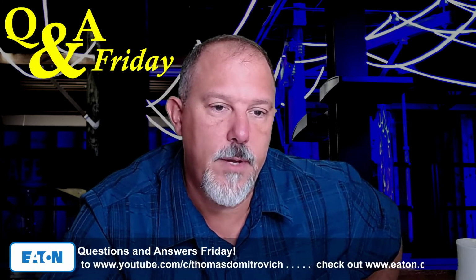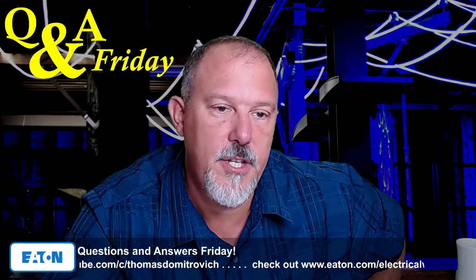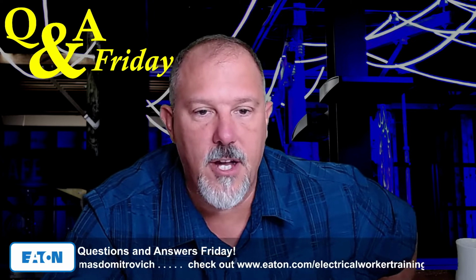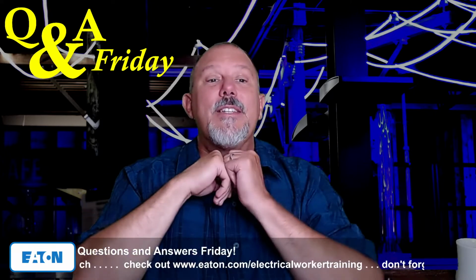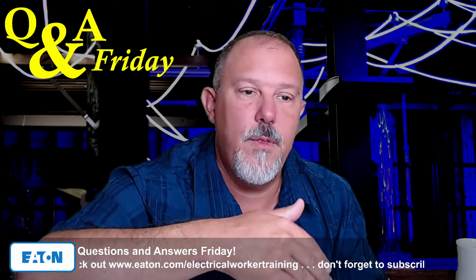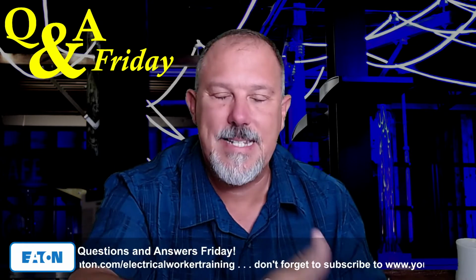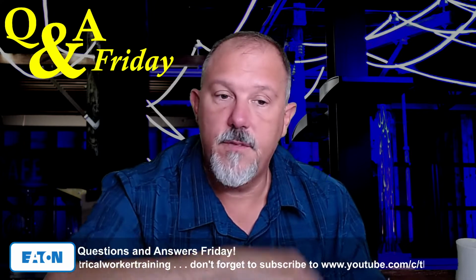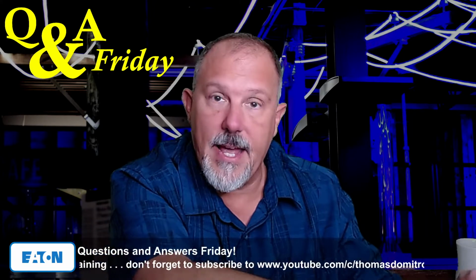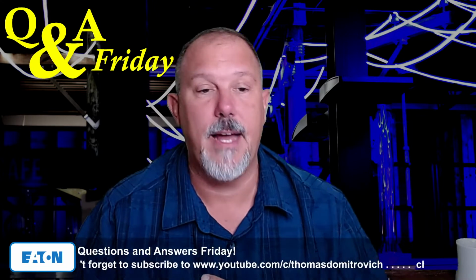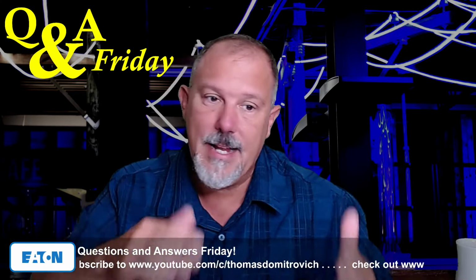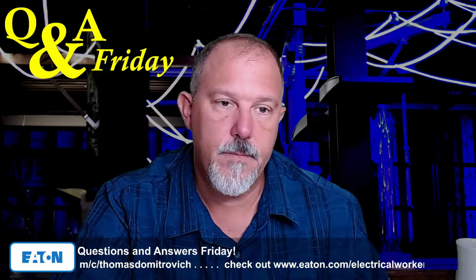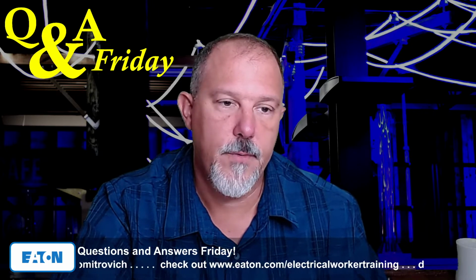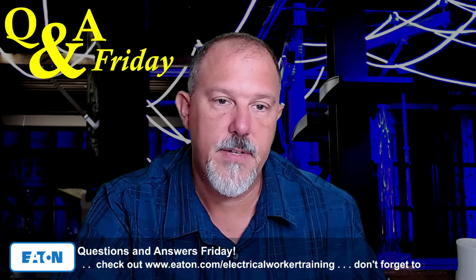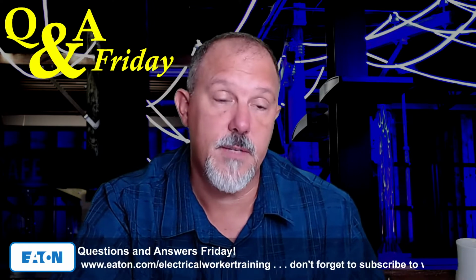As a result of 210, we now have people in the warmer climates whose new condensing units' GFCI breakers are opening and depriving the occupants of cooling during heat waves. So I think that's why NEMA and others supported the TIA that I believe would have addressed this. We also supported the TIA a while ago, but then the Standards Council rejected that from an emergency nature perspective. So in any case, I can't speak to how they would handle the GFCI, or how many people would die if they didn't have HVAC. I think it's a proven point that HVAC is important in many cases.